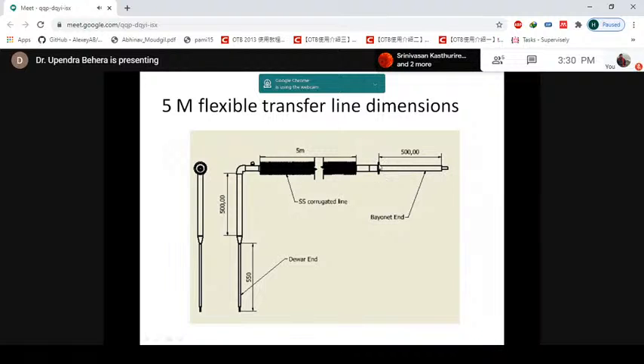What you can see is it is up to 500 meter, the vacuum extent is there. This will be used for their end application, and this goes to the storage dewar for their end application. Again, this is full super insulation, and this super insulation is extended up to the tip, where it will reach the system where you are utilizing this liquid helium.